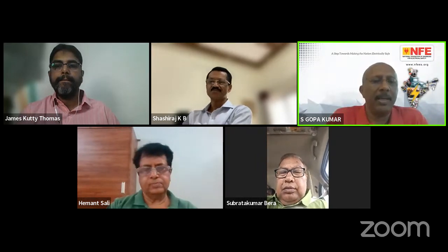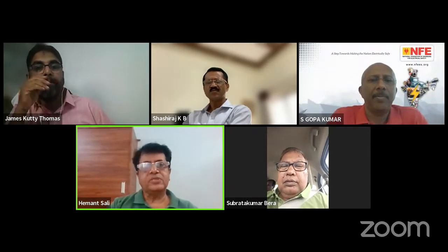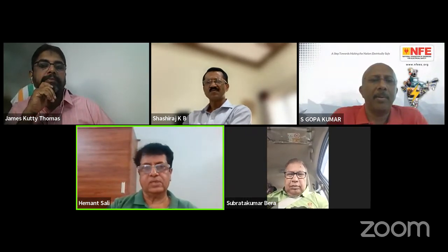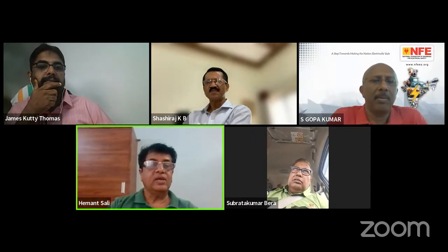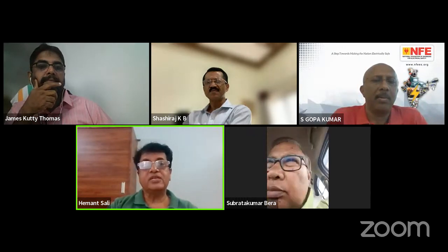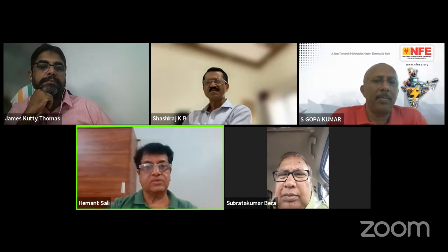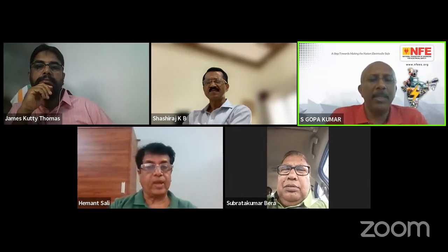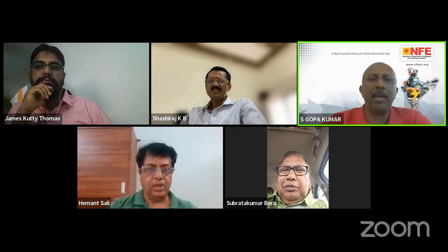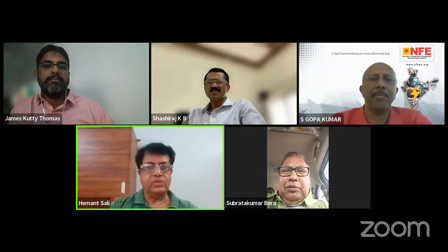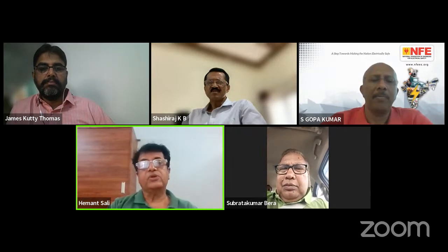If this is the facility in Karnataka, what about Maharashtra? I think if the person is designated for the particular task of work, and his name is given in that list, which he has to keep as a record, the electrical inspector can go and check, and even reject his name if he's not capable of doing that duty. So supervisor license or such things are not required. Okay, that means only a person having the supervisory license can be listed for this task? No, not necessarily. He need not have any supervisor's license. Only the company should designate him for the particular task of work.